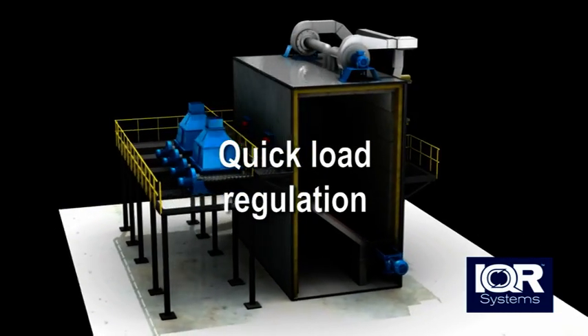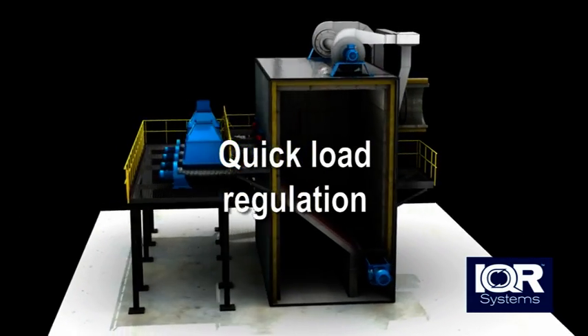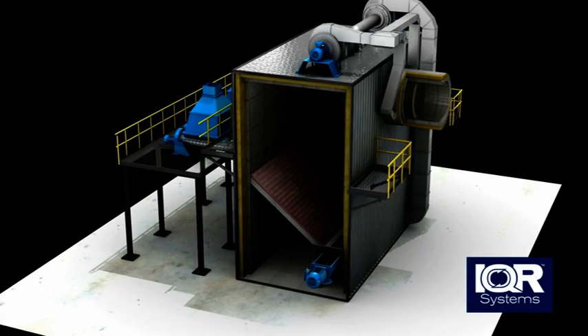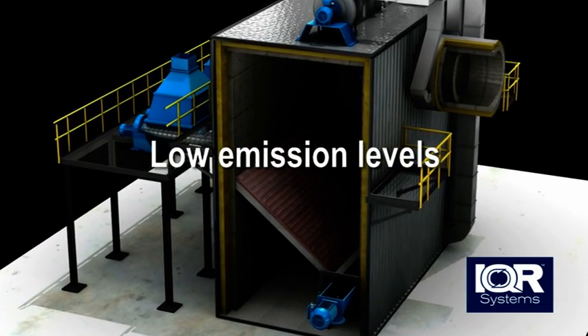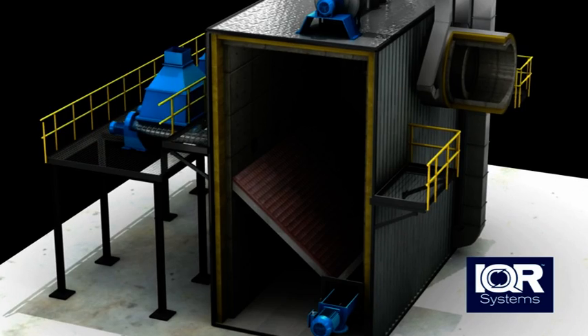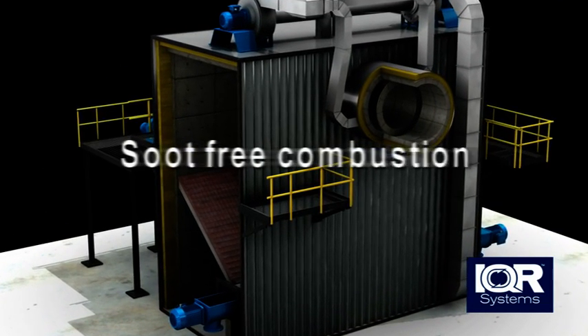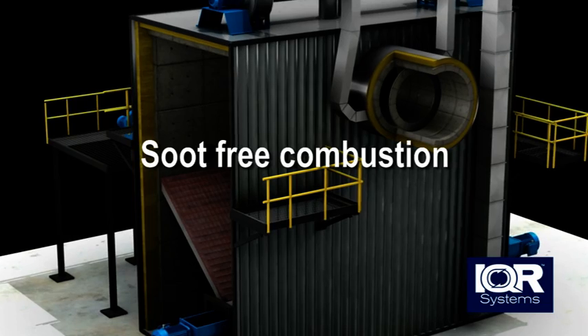With our technique, load regulation can be done quickly, while keeping emissions at a very low level. The 24 hour mean values of carbon monoxide are less than 20 mg per cubic meter flue gas. The combustion is free from soot.